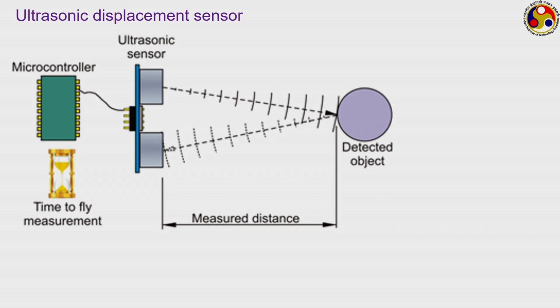That is precisely what we do in any sonic-based instrument, a sonic-based displacement sensor. The ultrasonic sensor produces a signal which goes to the object we want to locate, and then comes back. The time required for this signal to start from this point and come back is a measure of the distance from the sensor to the object.